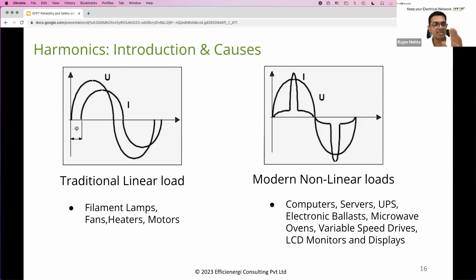The good news is that harmonics, in our experience at least, are not responsible very directly for electronic equipment failures. Sorry to bust that myth right now in front of you. I'll qualify my statement. If you see the impact on all the equipment on this slide where harmonics are causing impact, it's in terms of higher bills, production loss, or nuisance tripping of breakers. It's not electronic equipment failures.